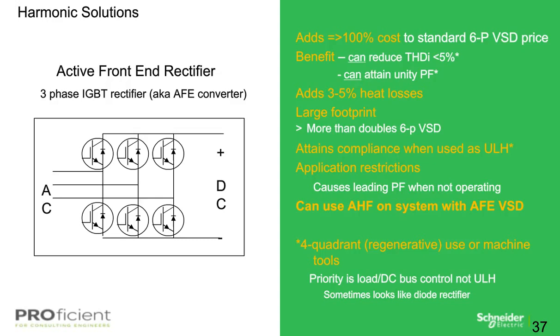However, when used on a VFD for a pump and fan application or any variable torque loads, the logic is designed to maintain the IGBT switching to optimize the current draw as close to the sine wave as possible, achieving less than 5% THDI. This also maintains near unity DPF. The next slide we'll also discuss will basically get into what is needed for the active front-end rectifier to minimize percent THDV.